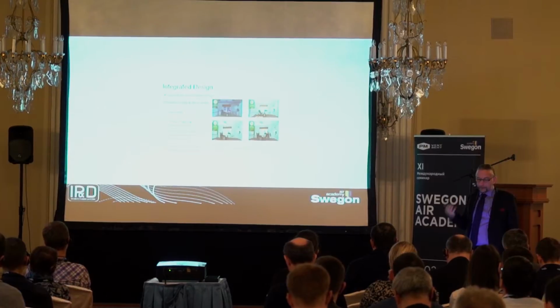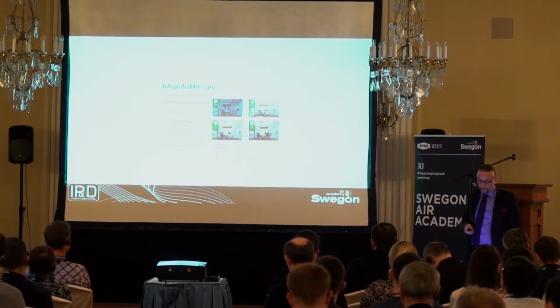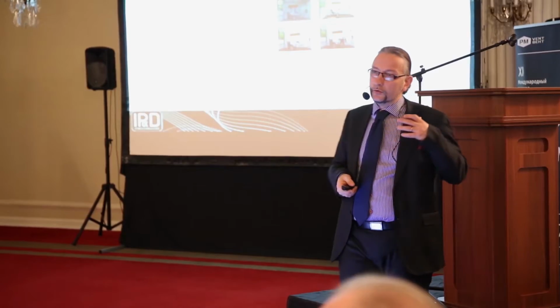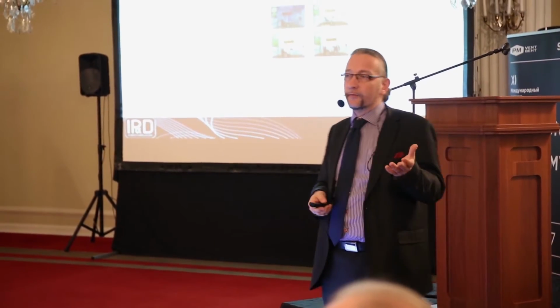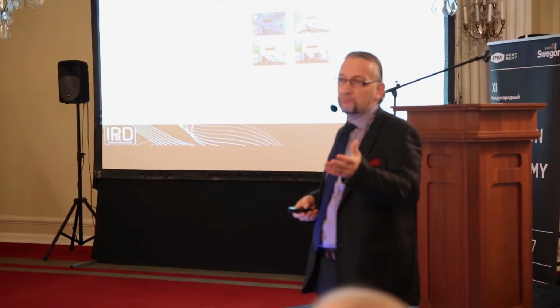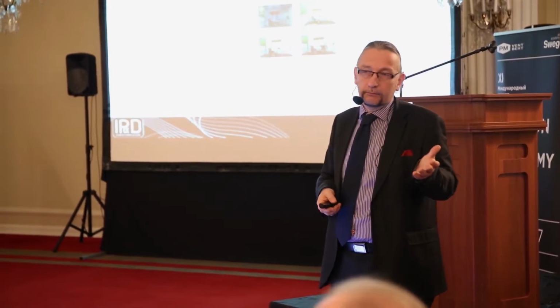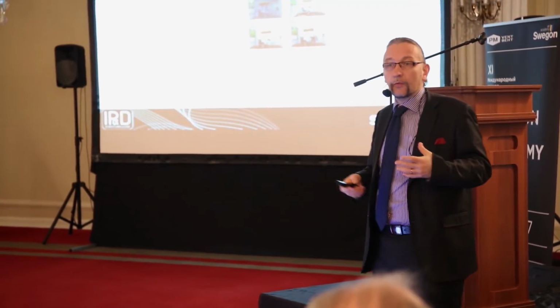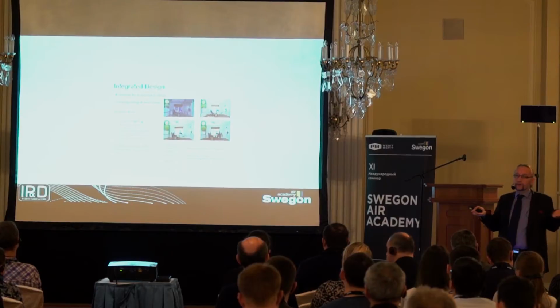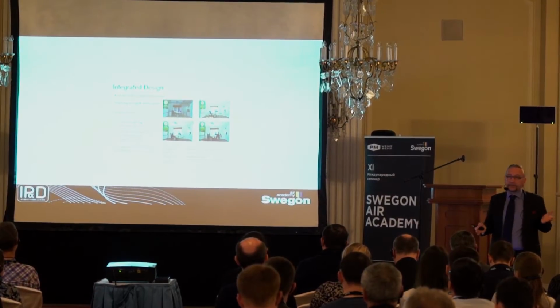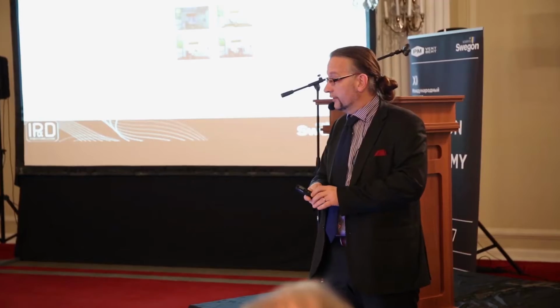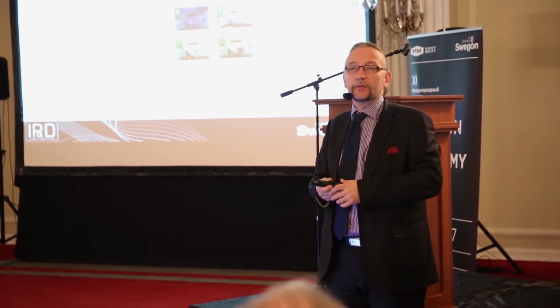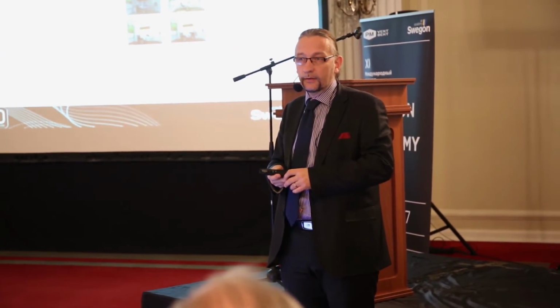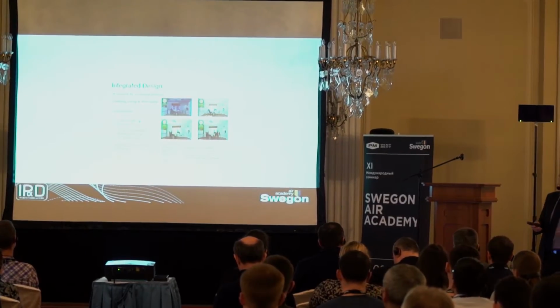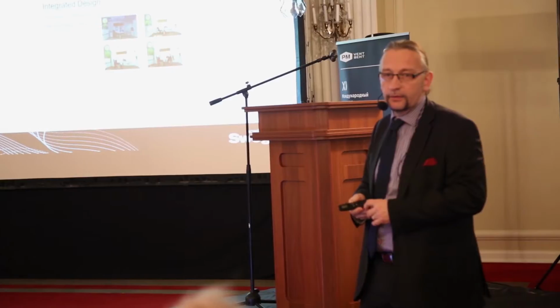So you have to have occupancy and air quality control. You want to reduce the temperature in wintertime, for instance, if nobody's in the room—normally 1, 2, or 3 Kelvin. In summertime, you let the temperature rise, maybe 1 or 2 Kelvin, when nobody's there. So if you accept 25 degrees in summertime during occupancy, you might accept 26 or 27 degrees when nobody's there. If you accept 20 degrees in wintertime, maybe you can accept 19 or 18 degrees if nobody's there.